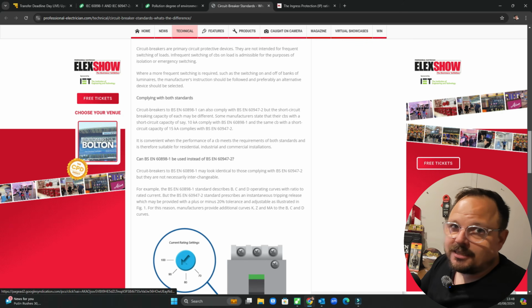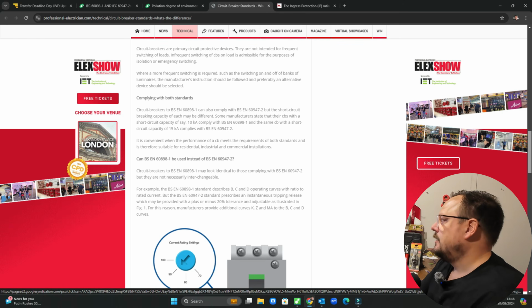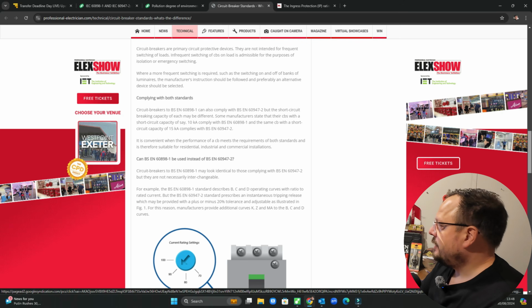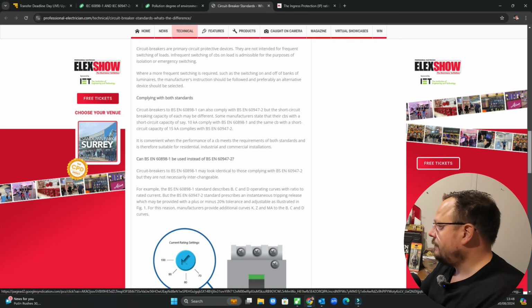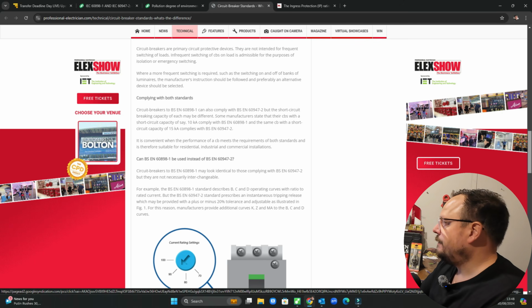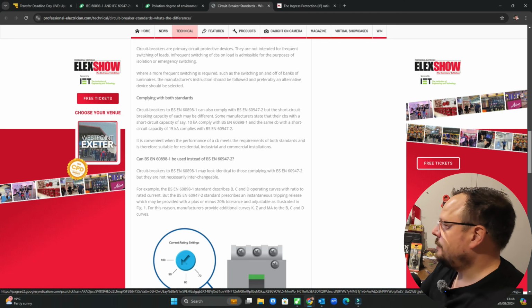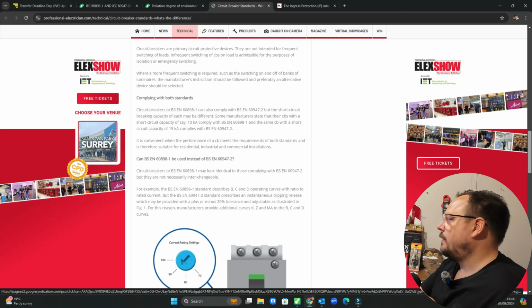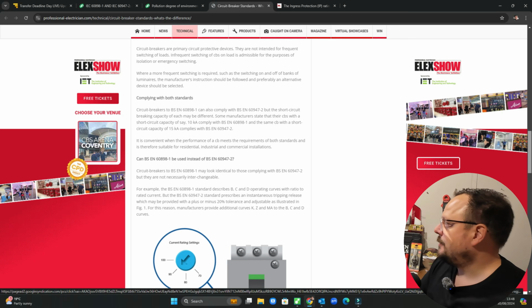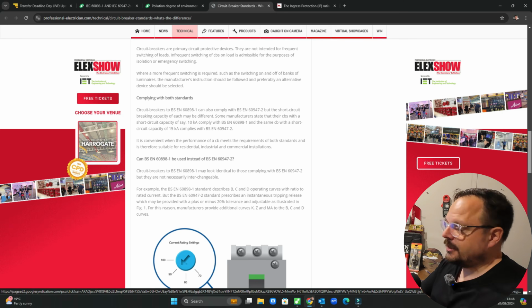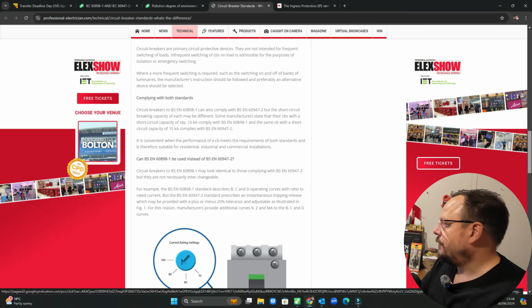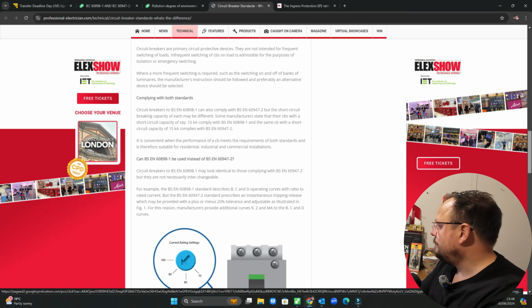So this is what we mentioned again, there are some products out there that do that. Circuit breakers to 60898-1 can also comply to 60947-2, but the short circuit breaking capacity of each may be different. Some manufacturers state that their circuit breakers with a short circuit capacity of, say, 10 kA comply with 60898-1, and the same circuit breaker with a 15 kA rating complies with 60947-2. So that's one to watch out for.